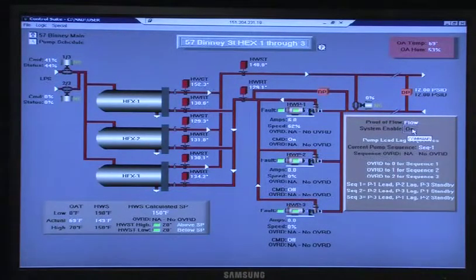You can disable it that way. When you get flow, the sequence will start to modulate the valves based on what you need. As far as the sequence goes, for the pumps, if sequence 1 is activated, you can see the key below: pump 1's the lead, 2's the lag, 3's the standby. You can see the current pump sequence, which is sequence 1. As you can see, pump 1 is actually running, so if pump 1 failed, pump 2 is going to come on.